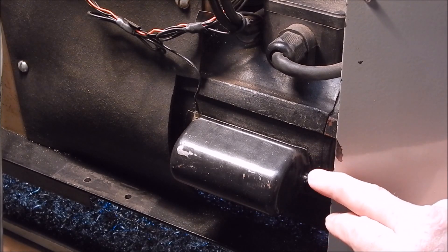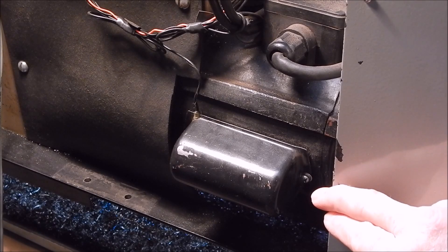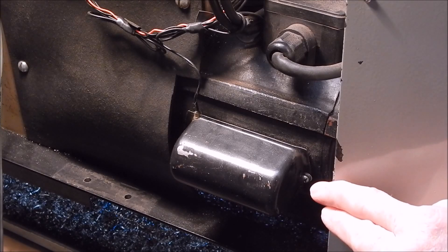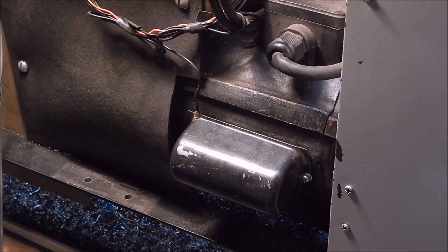The safe temperature on an AC motor is 50°C, but you can actually go to 65°C before things start going bad and you get meltdown. Once you go to 50–55°C you risk damaging the insulation on the winding, so you want to bail out reasonably early. Make up your own mind what temperature you want to go to, but at least this makes it very easy just to check.